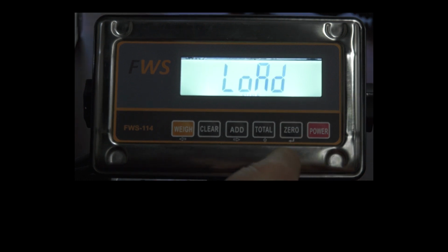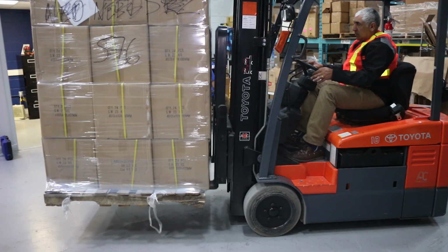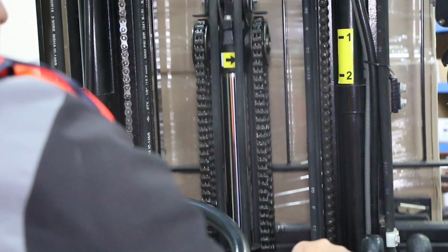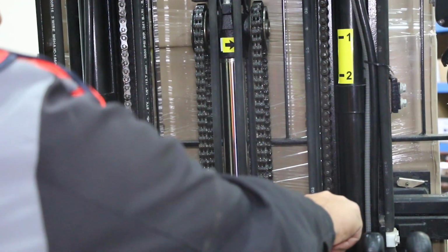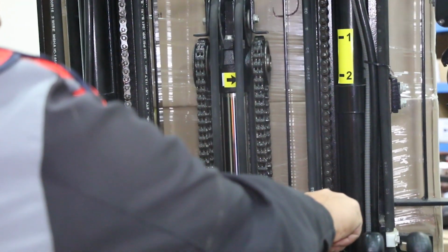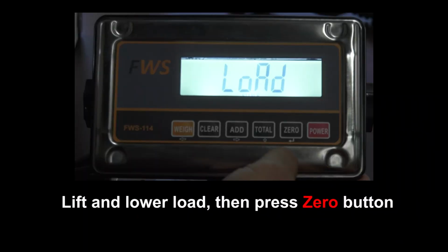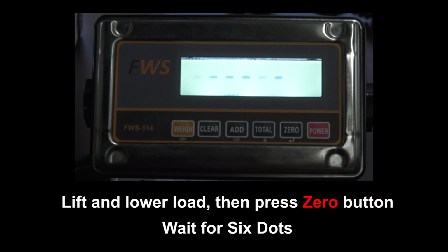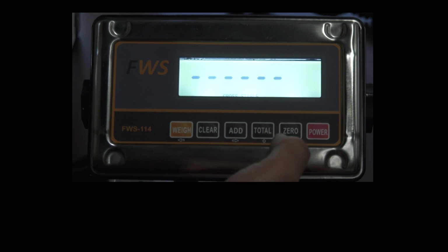The display will now say load. In this case, we are now going to lift the test weight and again raise to the number 1 on the decal and lower to number 2 to weigh the actual weight. Once you've raised and lowered the forks to weigh the load, hit the 0 button and you will get the pass notification. It will show the capacity, and after a few seconds, we'll get to the dots. You are now calibrated and ready to weigh your loads.